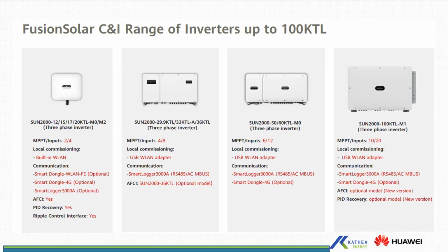For the commercial and industrial sector, the MPPT open circuit voltage is 1,000 volts. So our panels in a string must not exceed 1,000 volts, and the MPPT current is 12 amps. It means all panels in a string have to be wired in series, so you can maintain 12 amps. If you have a panel with a VOC, like now there are high power panels around 455, which have a VOC of around 47.5. If we round off to 50, your string length will be around 21 modules if you are using the 400 plus modules. So for local commissioning, for all inverters from 29.9 kilowatt upwards, you can use a USB WLAN adapter, which is supplied with the inverter.